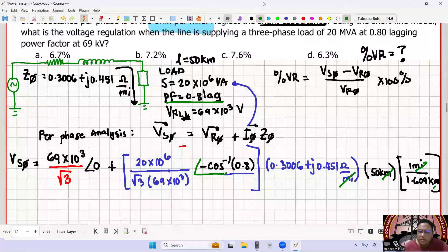Okay, diretso ko na para minsanan. Vs per phase now is equal to, okay mode 2 tayo, 69 times 10 raised to 3 over square root of 3, plus the quantity 20 mega all over square root of 3 multiplied by 69 kV bar angle negative arc cosine ng 0.8, multiplied by 0.3006 plus 0.451 I, multiplied by 50 multiplied by 1 all over 1.609.